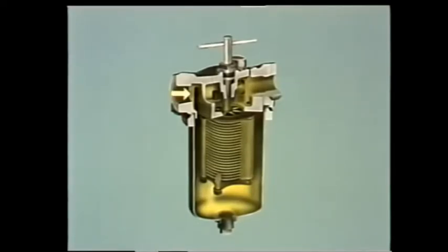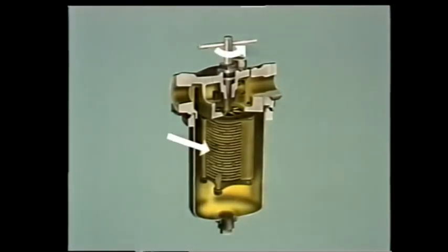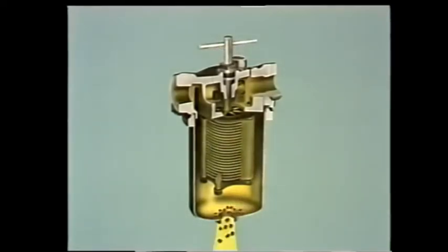Fluid enters through an opening in the casing, flows into the gap between the filter plates, and continues upward through the center of the discs. Any particles too large to fit between the filter plates will be trapped on the outside of the plates. Then, when the handle is turned, the discs move past the fixed cleaning blades. Particles that have collected on the discs are dislodged and drop to the bottom of the casing. The bottom of the casing must be cleaned occasionally and all dirt deposits removed.